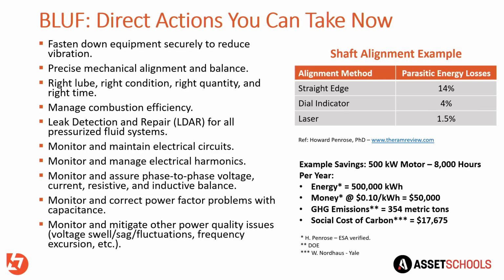It looks irregular. And to make this very simple, when you've got harmonics in the system and your voltage is no longer sinusoidal, in order to make up for those little depressions in the summation of your sine wave, the distorted sine wave, you have to make up for that with current. And current produces heat. In fact, I've got it in my course, I don't have it up here, but if you have a 3.29% average harmonic distortion, you're going to increase your energy consumption by about 20%. So even a little tiny bit of distortion will have an impact.